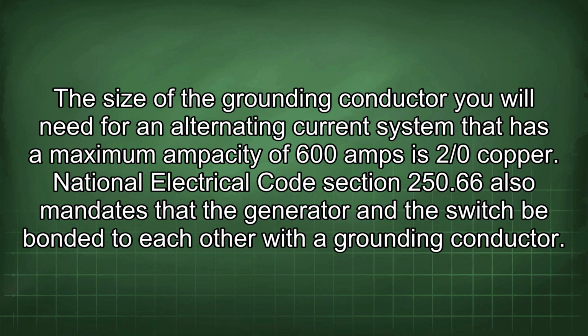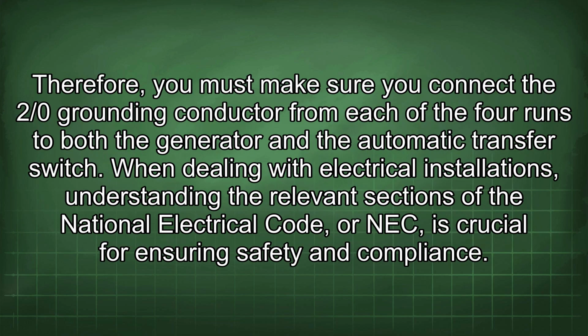National Electrical Code Section 250.66 also mandates that the generator and the switch be bonded to each other with a grounding conductor. Therefore, you must make sure you connect the 2/0 grounding conductor from each of the 4 runs to both the generator and the automatic transfer switch.